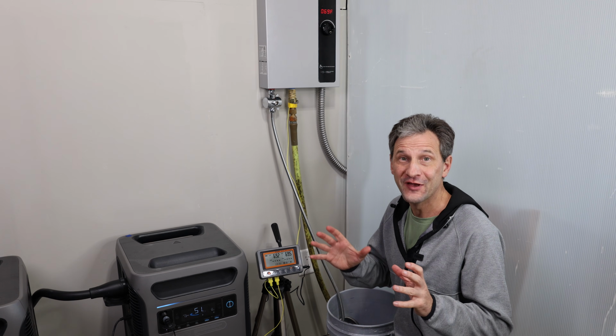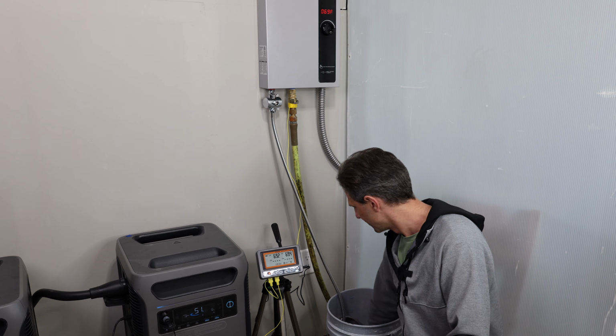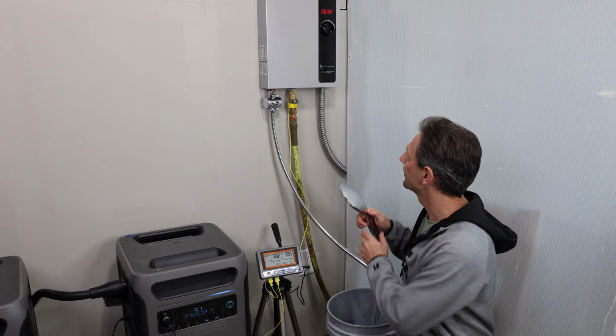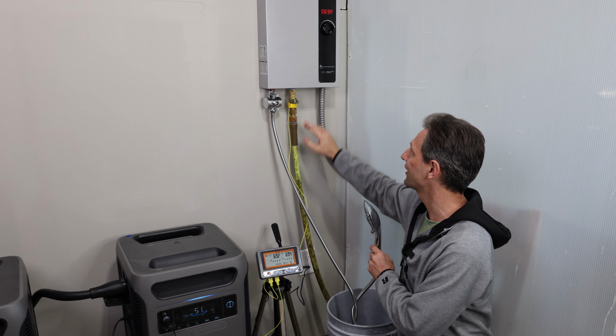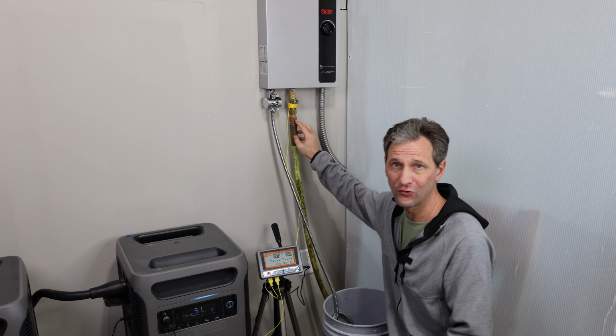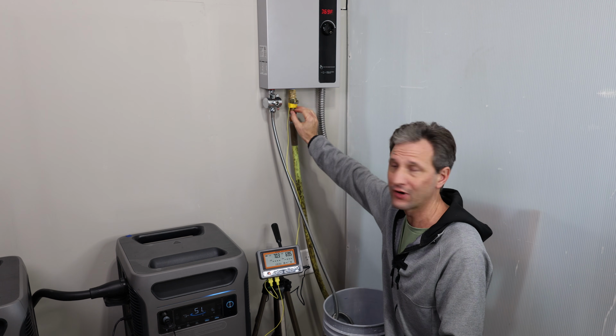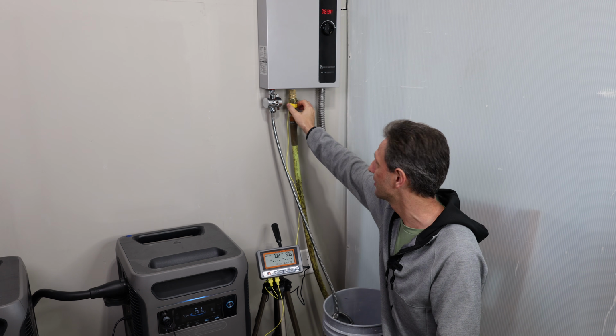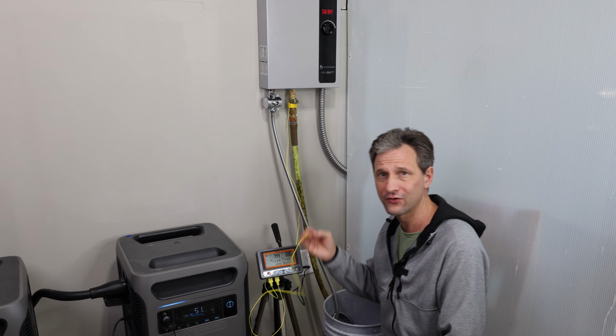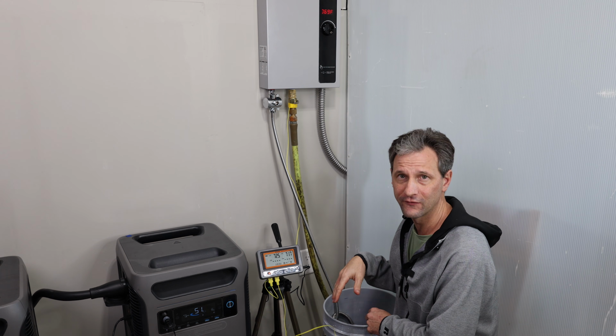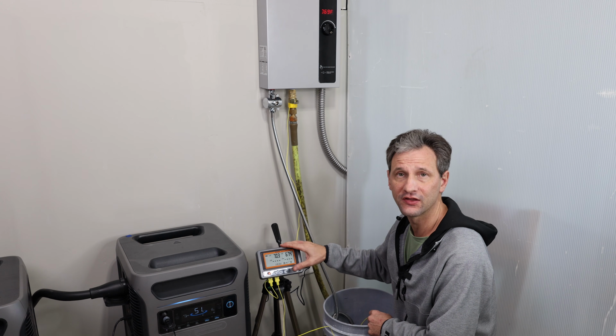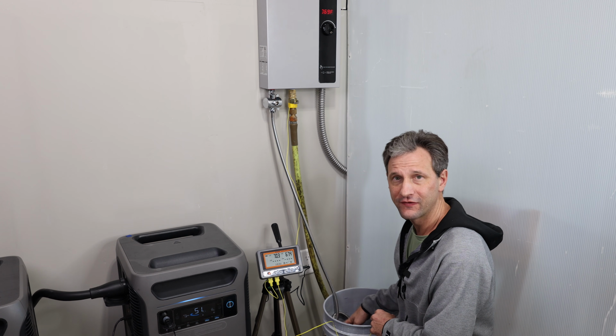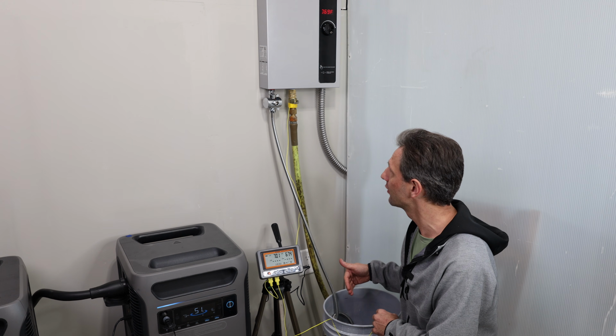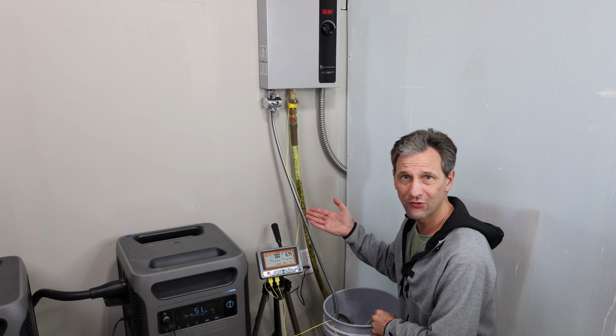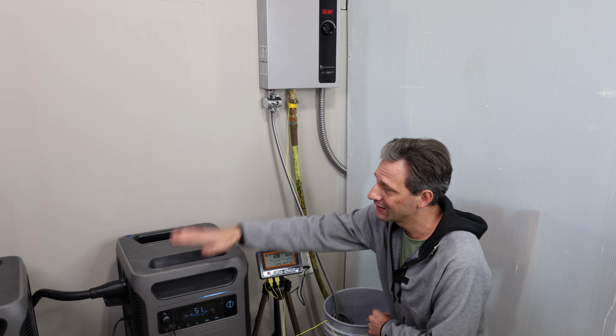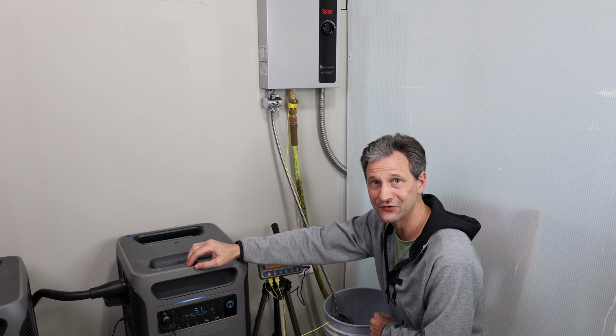So pretty simple. I made a really simple test setup here. I have a shower connected directly to the output, and I just ran a hose for now to the input. The hose will deliver our cold water. I have a thermocouple taped to this brass fitting, and that'll give us a pretty good idea of the input temperature. Then I have another thermocouple that I'll put in the bucket to measure the temperature of the water in the bucket. I'm just using this data logger to collect the information from the thermocouples. I've marked off gallons in the bucket so I can measure the flow rate of the water coming in. So we'll be able to determine the temperature rise, the flow rate it can deliver, and we'll also track how much power we're pulling from these units.